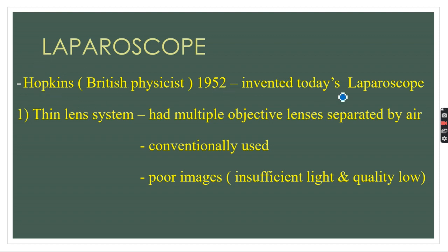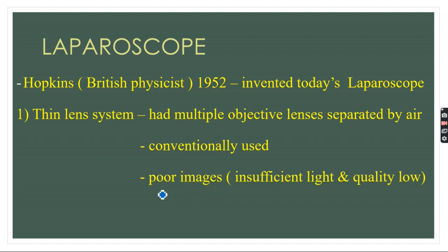There are two basic systems. Previously, the thin lens system was used. In this type of laparoscope, there were multiple objective lenses whose images were separated by an air column — this was the conventional system. However, it produced poor images due to insufficient light transmission, resulting in very low-quality images through the thin lens system laparoscope.